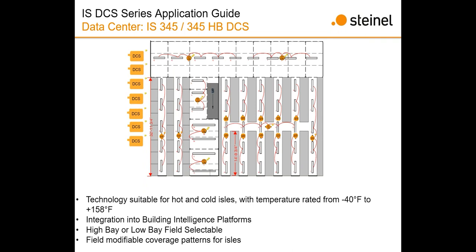These are infrared sensors with 2 pyros in them, meaning they have 2 sensors built in. One looks one direction down the aisle and the other the opposite direction, so you have very good coverage. Notice that in some areas the sensor is only looking in one direction—that's because all the sensors ship with that plastic insert that fits underneath the lens, so you can have it look in only one direction if you only need an aisle starter.